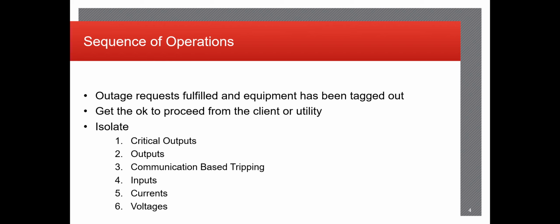This is usually very bad because if you misoperate a piece of equipment that's not going to be a part of the outage, that could be detrimental to customers, to the client's procedures, everything like that. So by taking out the critical outputs first, you lose most of the risk of any misoperations occurring. The second is the rest of your outputs. This can be any non-operative output that the relay may utilize.